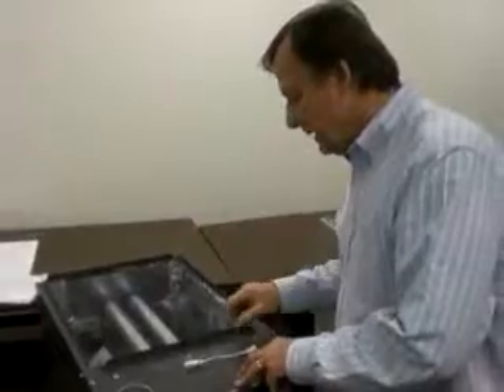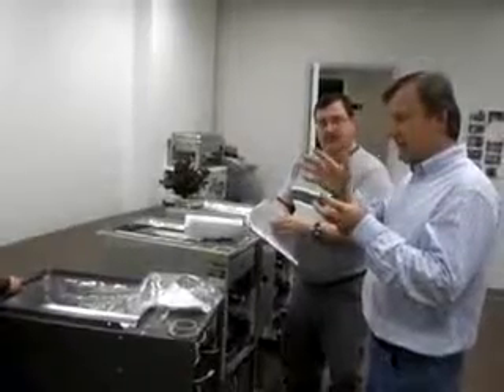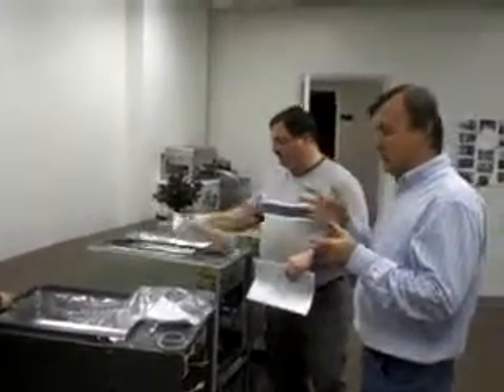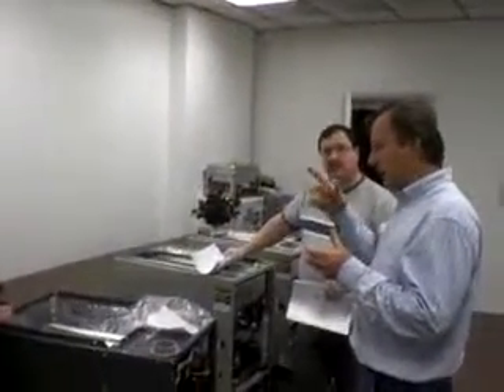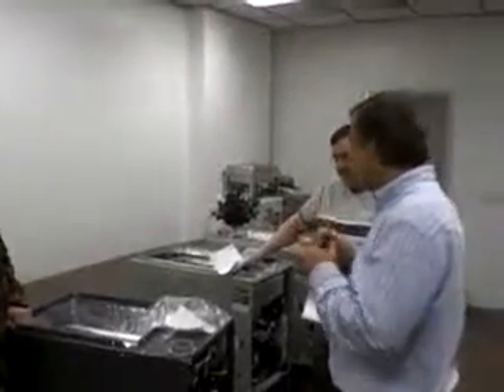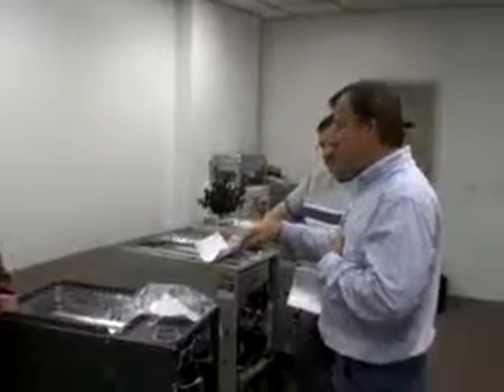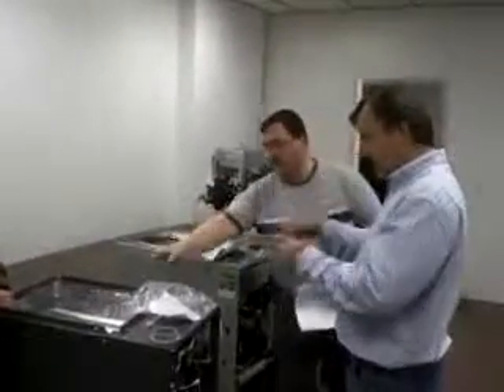This furnace, when we opened it, we inspected it to see if there were any obvious defects, and lo and behold, we had a defect in the recuperative cell, the secondary heat exchanger. Trane tests every furnace before it leaves the factory. At the end of the assembly line, they put it on a turntable, they hook it up to a vent system, they hook it up to gas, they hook it up to electric, and they perform, I believe it's a 16-point test. How long is that test? It only takes a few minutes, like 1.5 or 2 minutes. Okay. But they're able to check all of these operating points. With that kind of defect, one of our furnaces would never have left the factory. No. This was packaged, opened here with a defect in the heat exchanger.